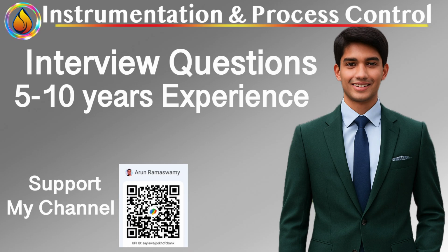What's the difference between Modbus RTU, Modbus TCP, and OPC UA? Protocol, medium, speed, use case. Modbus RTU: serial RS485, 9.6 to 115 kbps, legacy field communication. Modbus TCP/IP: Ethernet, modern DCS and PLC integration. OPC UA: platform independent, Ethernet, secure object-based enterprise connectivity and cybersecurity compliant. OPC UA is preferred in new projects for secure, scalable integration under IEC 62541.